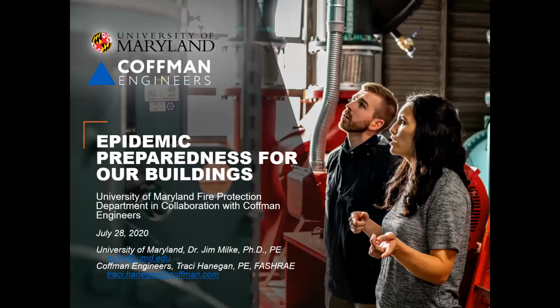Yeah. We're recommending that people try to get at least a MERV 13 as a minimum level of filtration. If you can do better, that's great. MERV 14 is the minimum level. A MERV 13 filter, kind of the minimum. The 14 is the minimum level for a healthcare facility. We used to call that a 90 to a 95% efficient filter. And then of course there's HEPA, and we do have people that use various levels of HEPA filter, especially when they're trying to filter out the really fine particulates for like a wildfire event and cut down on the PM 2.5 level in a space.